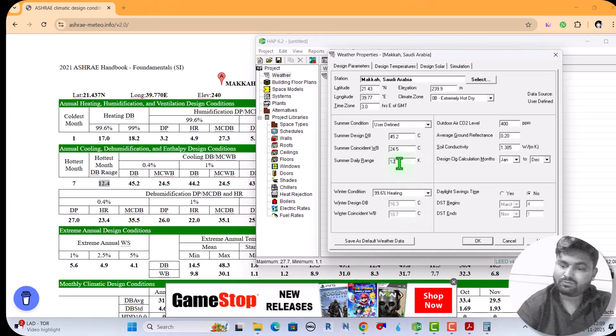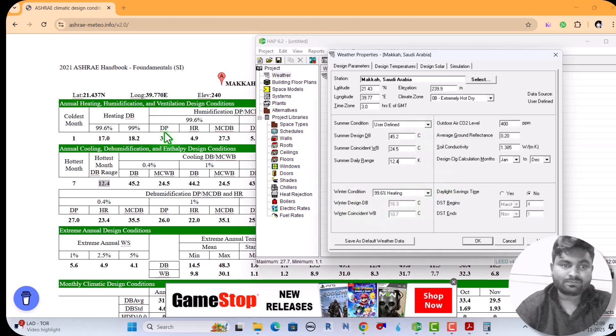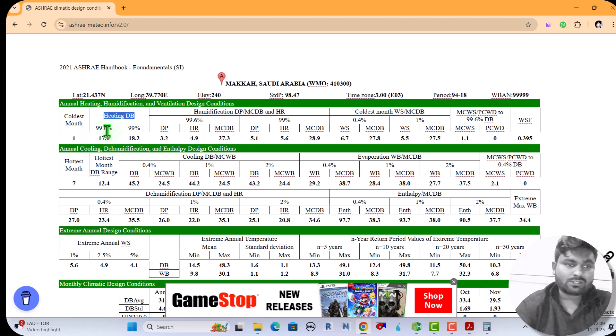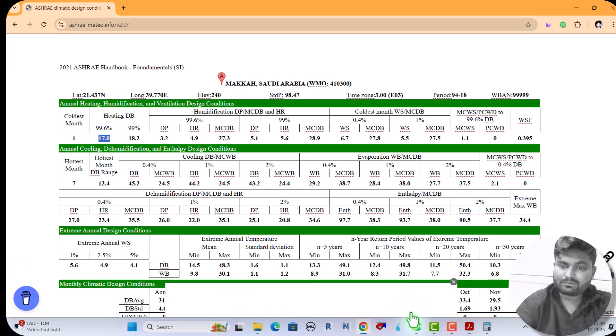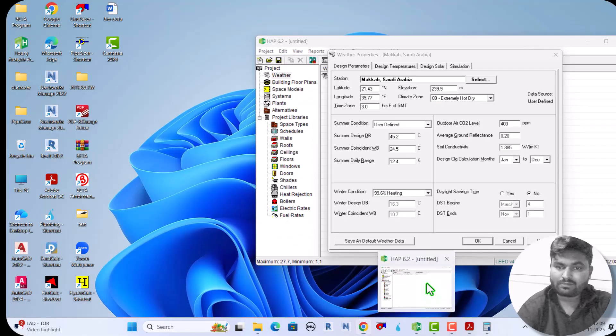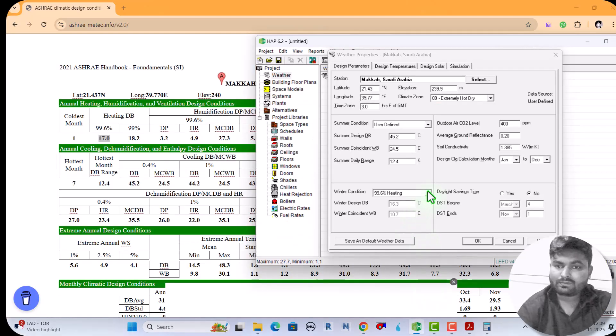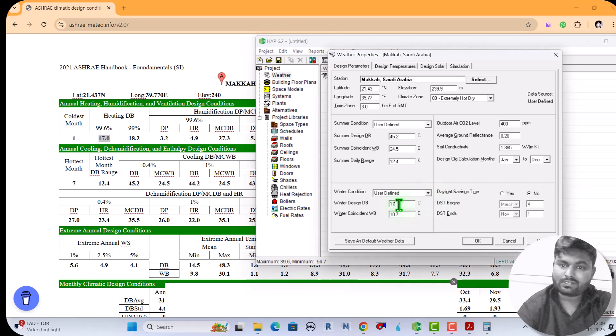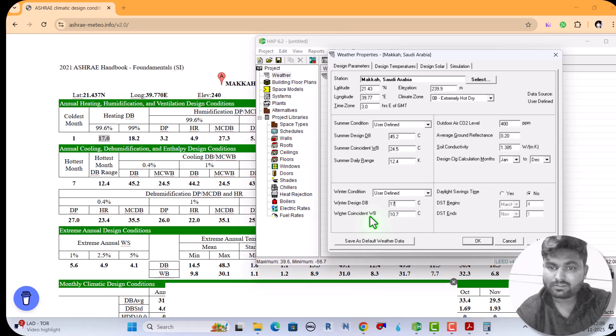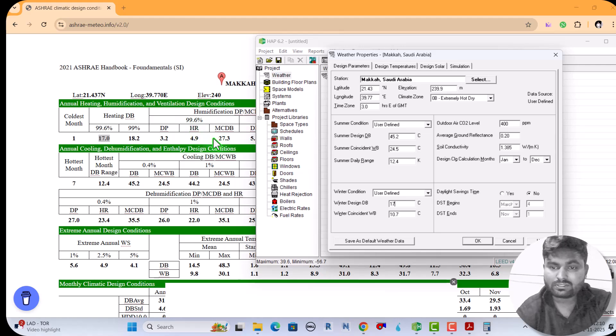Now for heating, see here heating dry temperature, 99.6% if we are considering, then the heating temperature is 17 degrees Celsius. Also we can take 17 degrees Celsius user defined. And what about the winter coincident wet bulb? Here it is not mentioned. See, winter dry bulb, winter coincident wet bulb is not mentioned here, but dry bulb is mentioned, so we have to calculate.